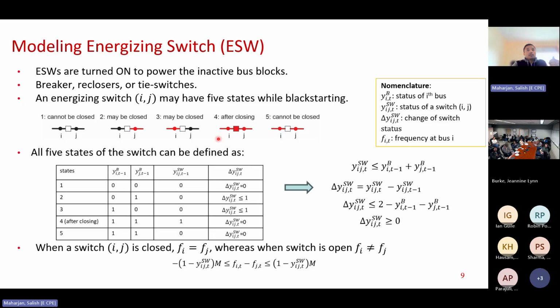So we can represent all these 5 states in mathematical equations, and those equations are shown by a bunch of constraints shown here. And the important thing is this: when an energizing switch is closed, basically the frequency information at one block is also transferred to the other bus block. And if it is open, then both bus blocks could have different frequencies, right? So this condition of different frequencies can also be established by using this big M method shown here.